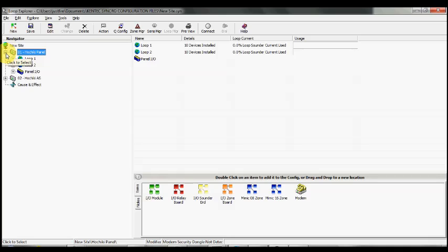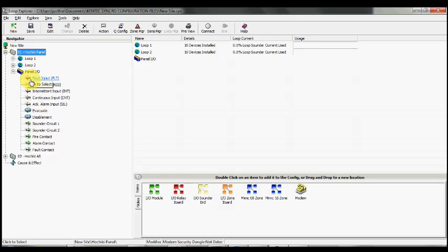So the first thing we need to do is select the input that is going to cause the test facility to occur. So this might be something that we install inside the panel, like a key switch which we wire to one of the 5 default inputs on the control panel, which can be found along the terminal bar along the top.